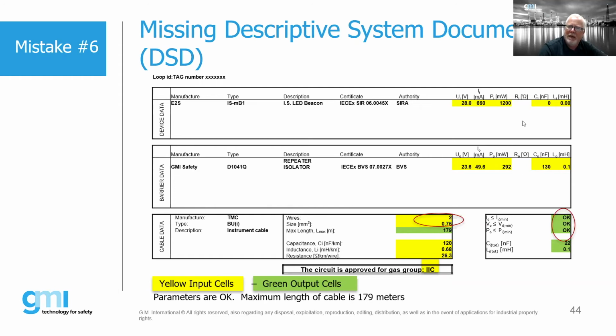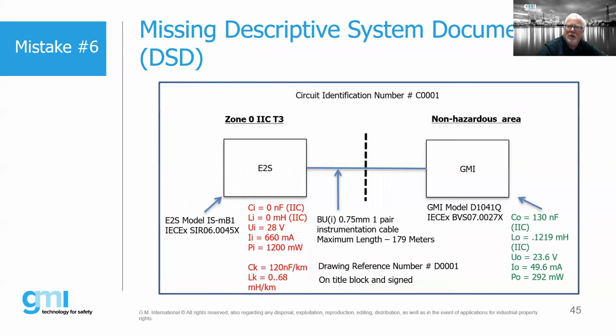This tells us, based upon this beacon in conjunction with this barrier, our maximum length of cable is 179 meters based upon a gas group of 2C. Now, that's why we want to see in our DSD the information as far as how long this cable could be without violating the parameters that we've set forth. So if we don't know that information, then again, as an inspector, how do we know?